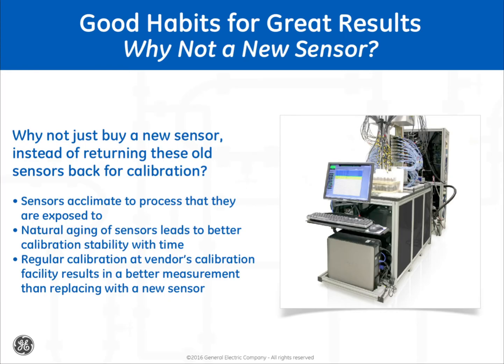Why not just buy a new sensor instead of returning these old sensors back for calibration? Sensors acclimate to the process that they are exposed to. This, along with the natural aging of the sensors, leads to better calibration stability with time. For these reasons, whenever possible, regular calibration at the vendor's calibration facility will lead to a better measurement than replacement with a new sensor.